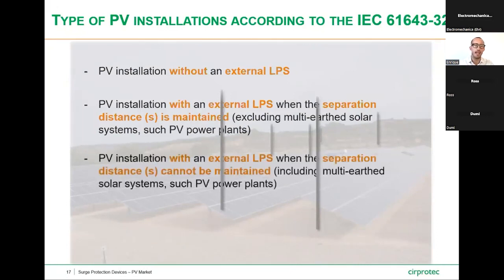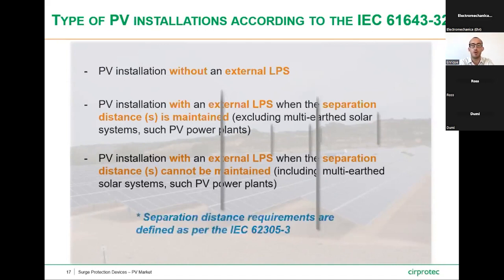And then the last PV installation type the IEC is defining is the PV installations with an external LPS when the separation distance cannot be maintained. This case is including the multi-earth solar systems such PV power plants. Let me inform you, just in case you would need to check and for your reference, the topic about the separation distance. The requirement belonging to this distance are clearly defined as per the IEC 62305-3.